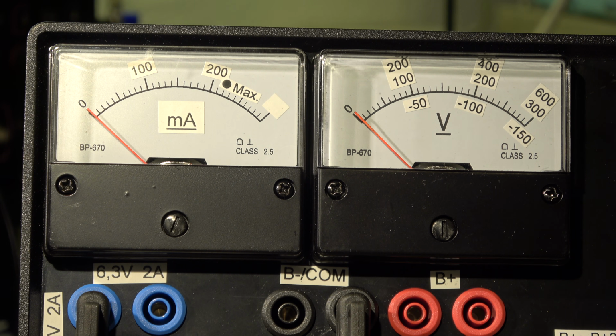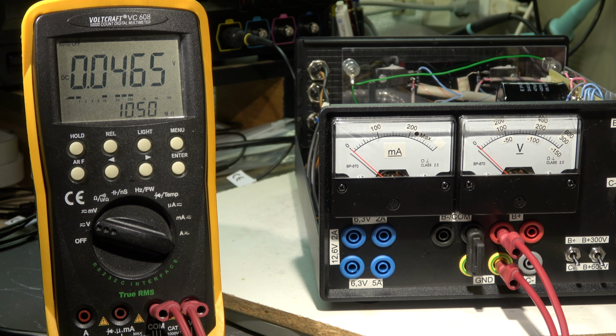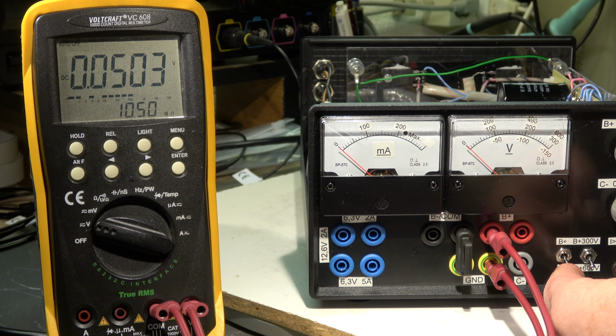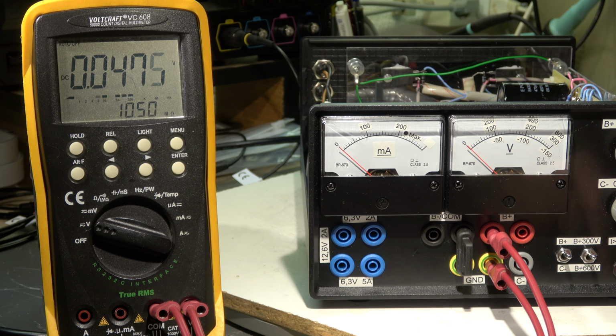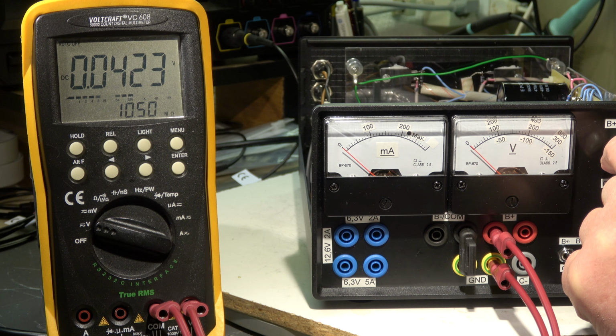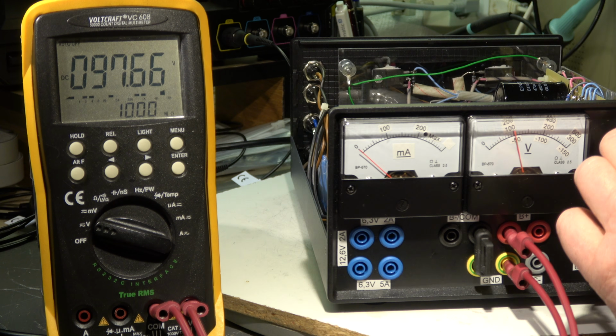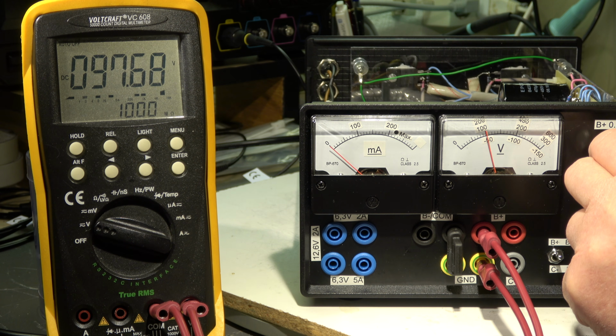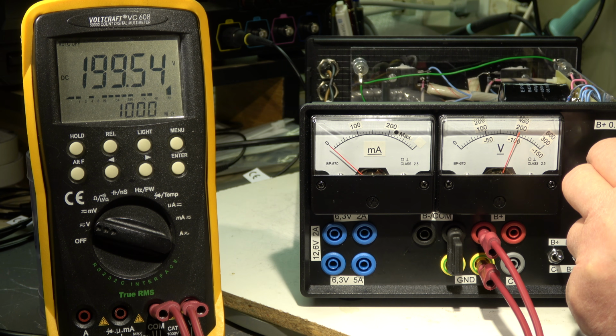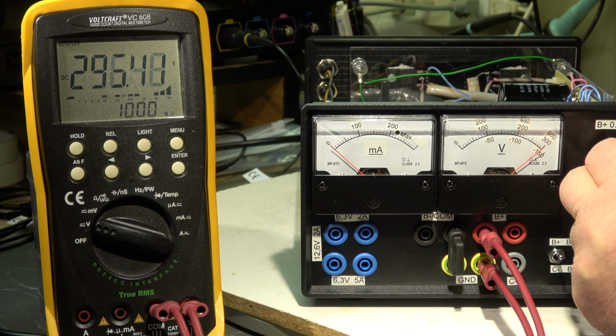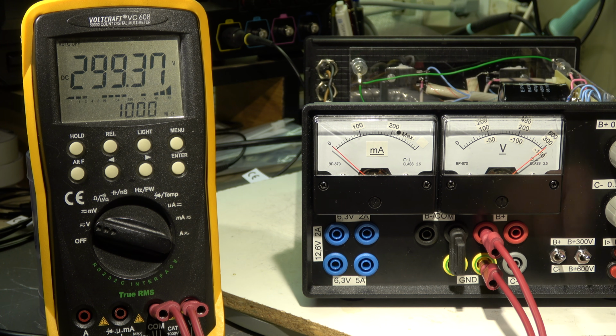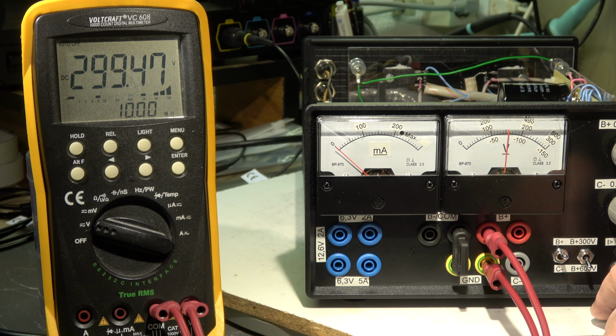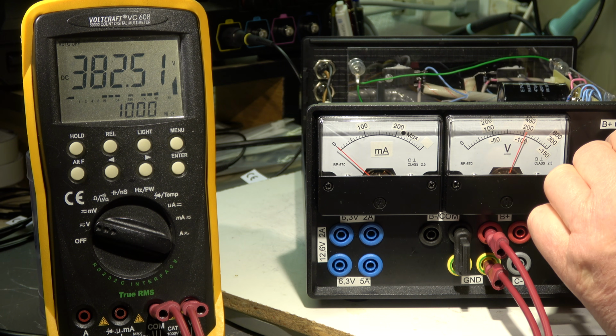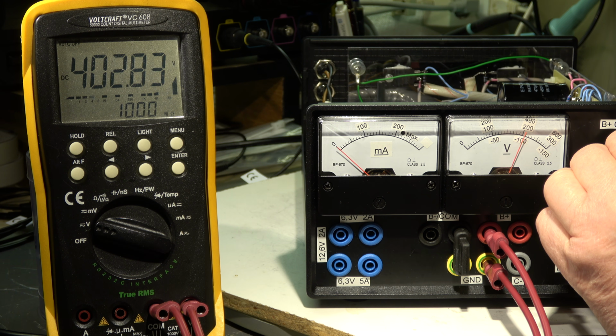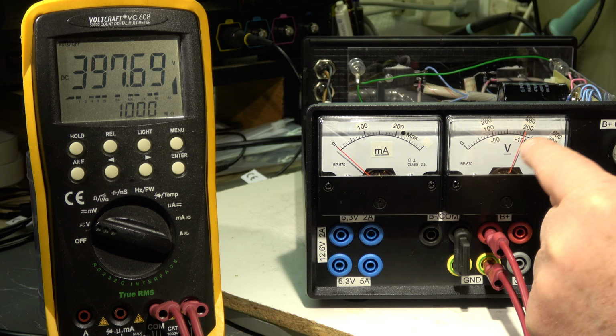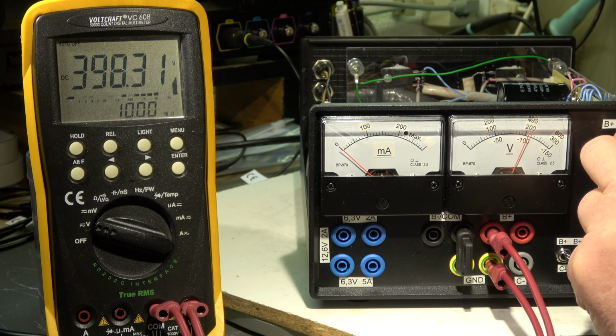So it's ready now and we can do some tests. Now some checks of the accuracy. First the B plus. The meter is set to measurement of B plus. Scale is 300 volt. It's 100, 200, 300. When I go to 100, the instrument has a little bit of non-linearity. 200, it's more accurate, and 300, then it is okay. It's non-linear, this one also. Go to 600. That means 300 is exactly in the center, and 400 volt DC output here is okay. 398. It's smaller than the error in the pointer, so this is okay.